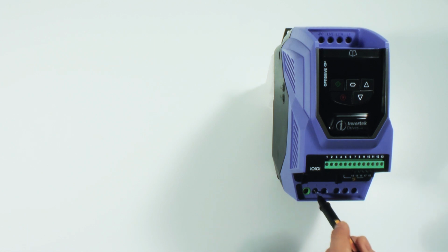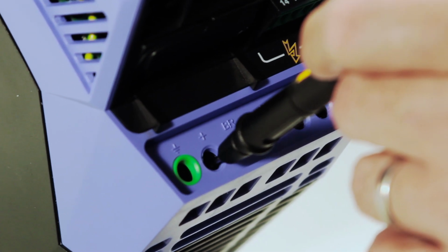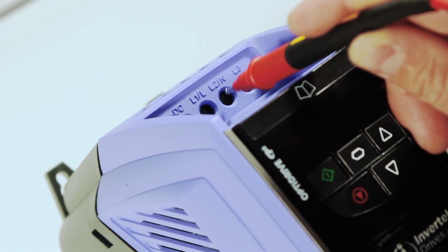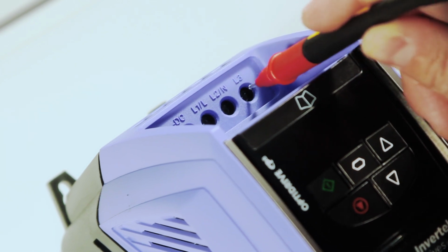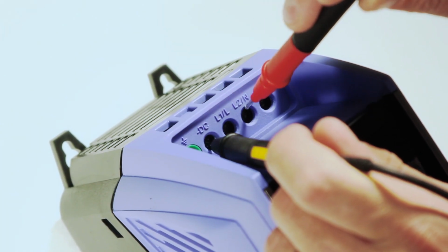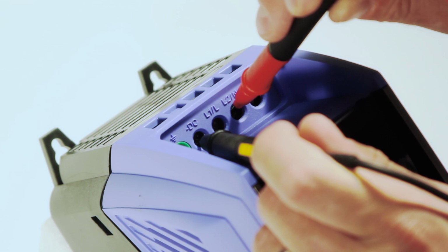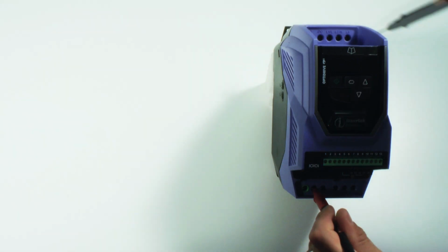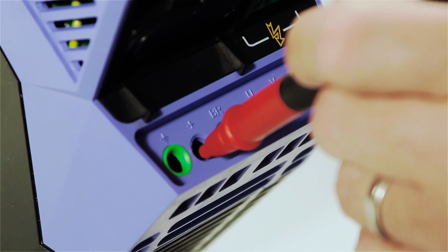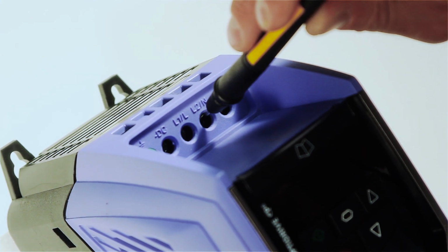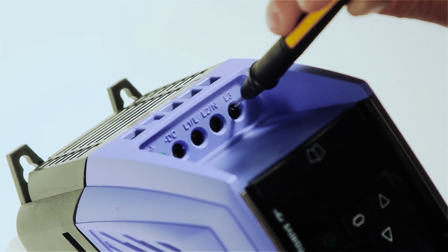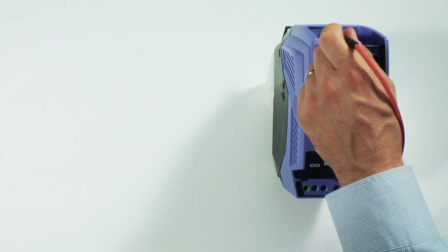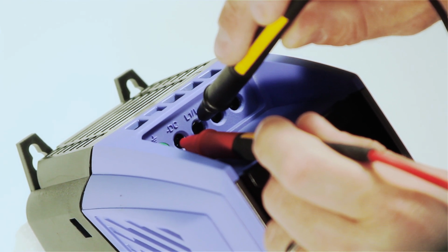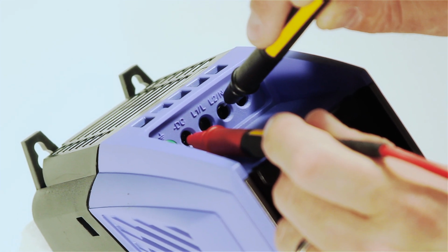Rectifier thyristor check. Place the black lead on the plus DC bus point and measure with a red lead to L1, L2 and L3. Place the black lead on minus DC bus point and measure with a red lead to L1, L2 and L3. Place the red lead on the plus DC bus point and measure with a black lead to L1, L2 and then L3. Place the red lead on the minus DC bus point and measure with a black lead on L1, L2 and then L3.